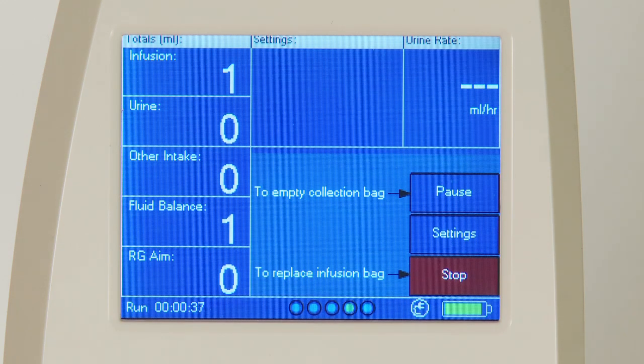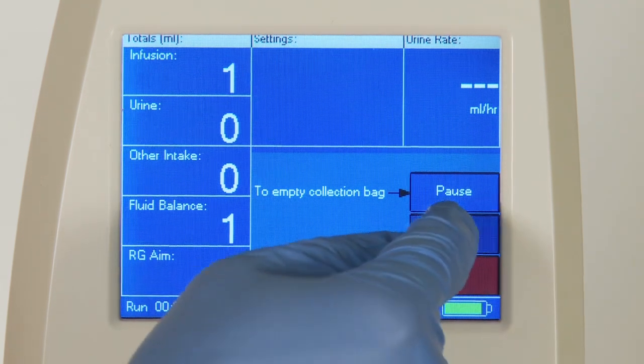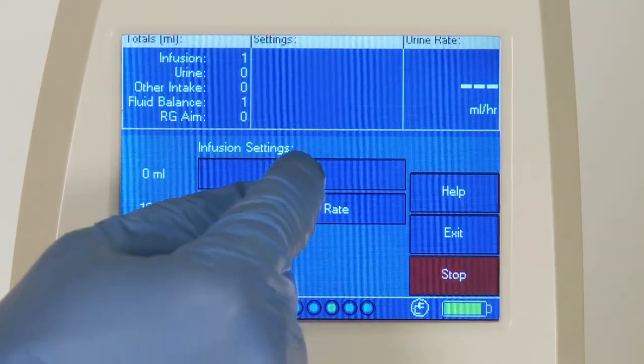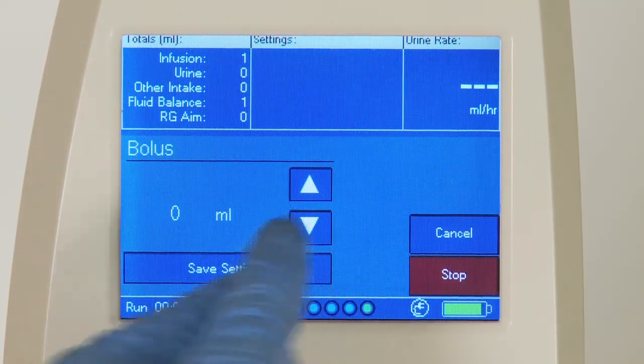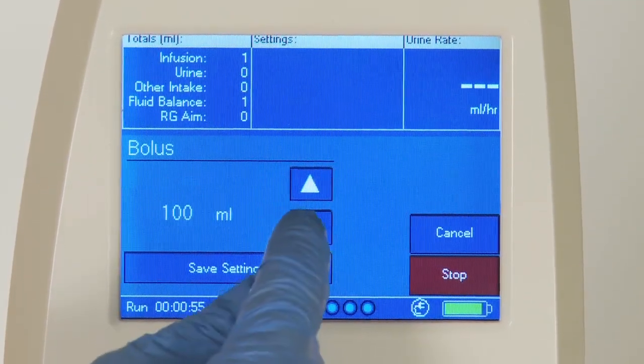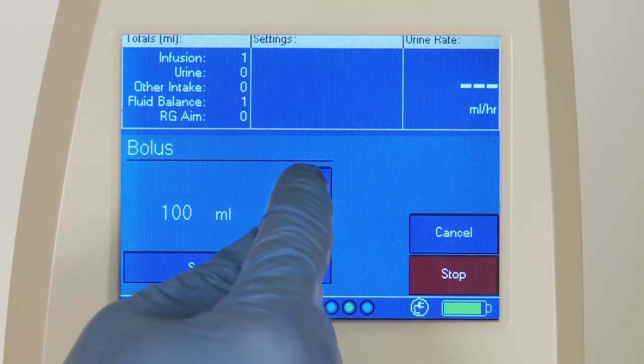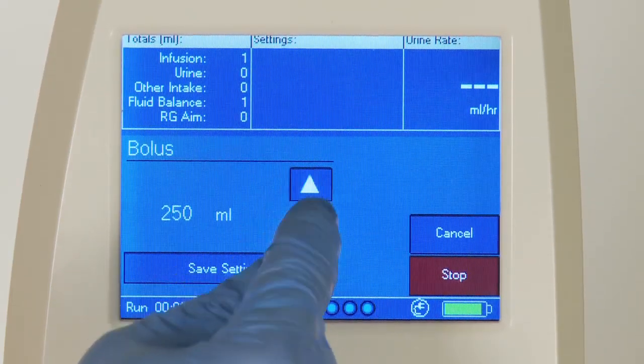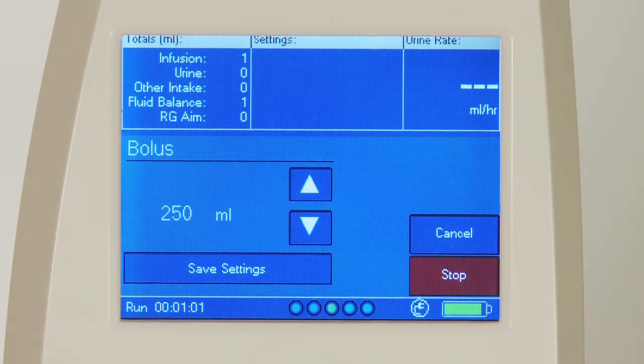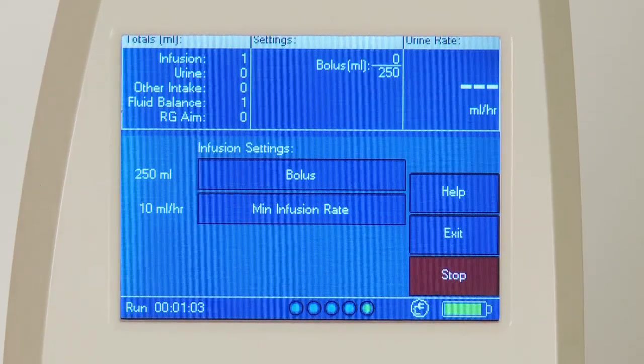Bolus allows you to infuse an additional bolus of hydration fluid over a 30-minute window. This fluid is over and above fluid infused for matching. To adjust the bolus, touch the Setting button, then Infusion, then Bolus. Use the arrows to adjust the bolus setting up and down. When you have reached the desired setting, touch Save Setting to store the setting. If you do not touch Save Setting, the setting will not be stored. You will now see the bolus setting appear in the Settings section.